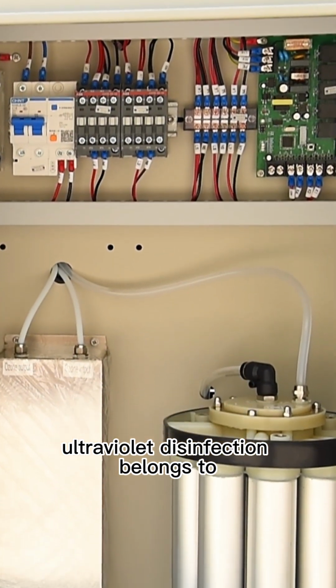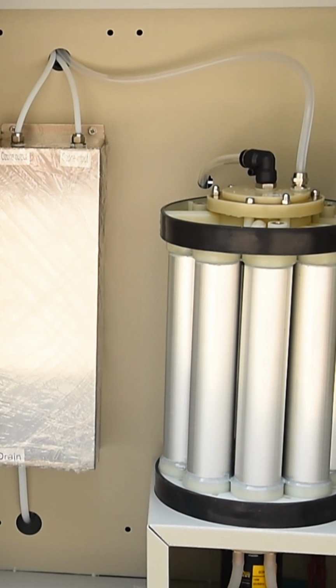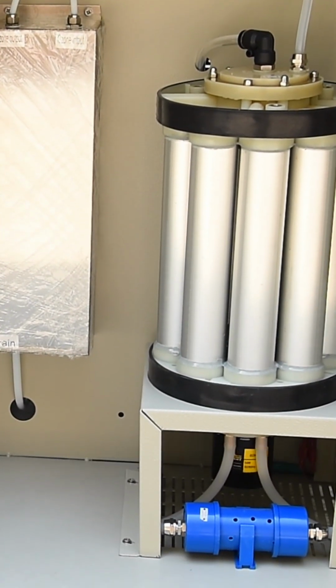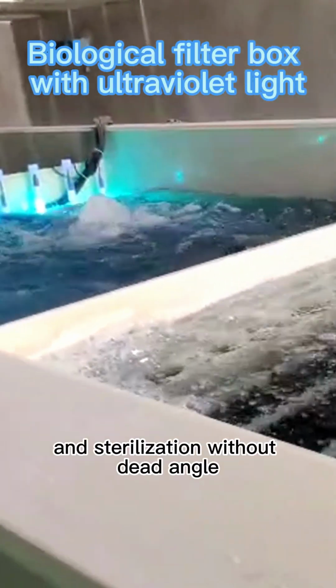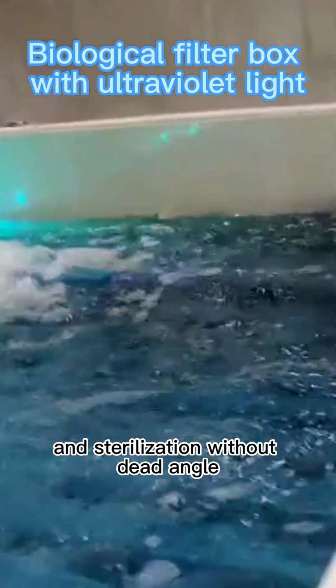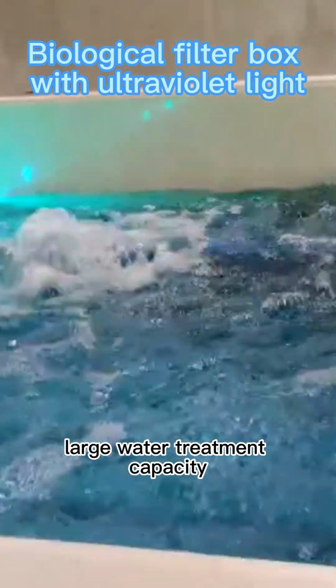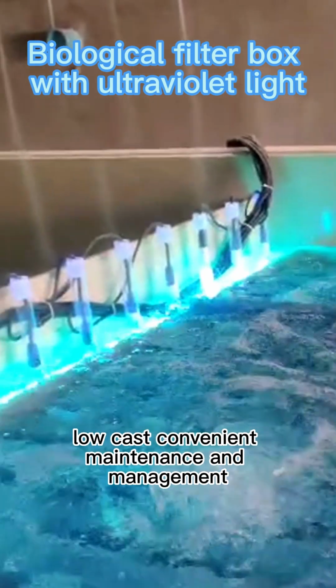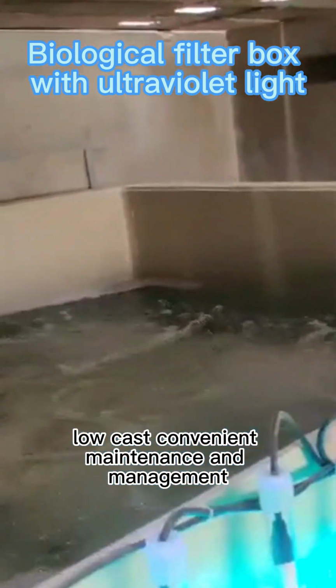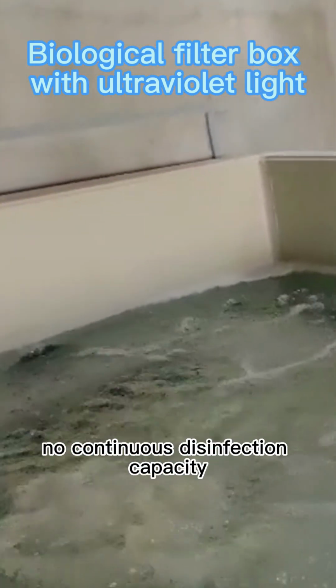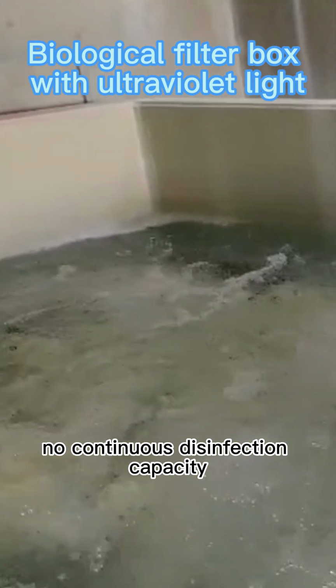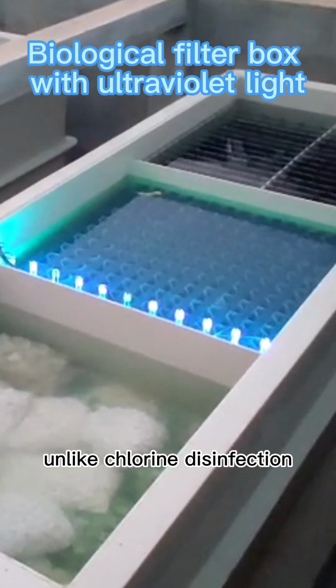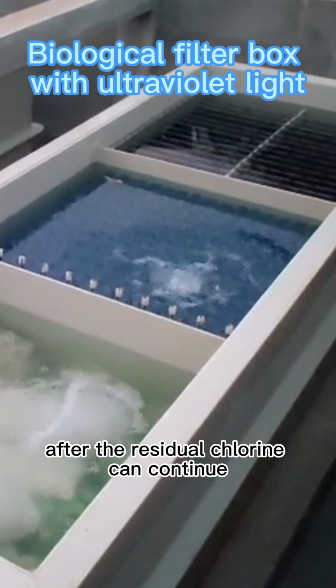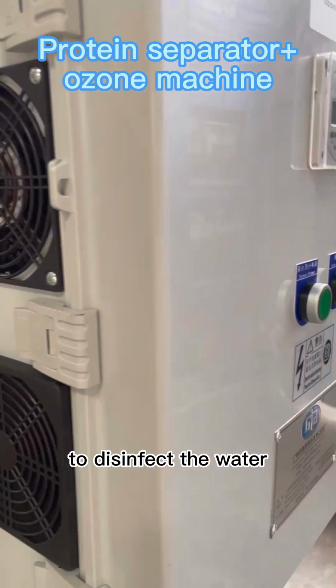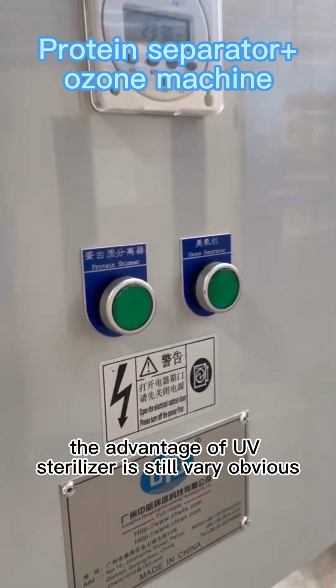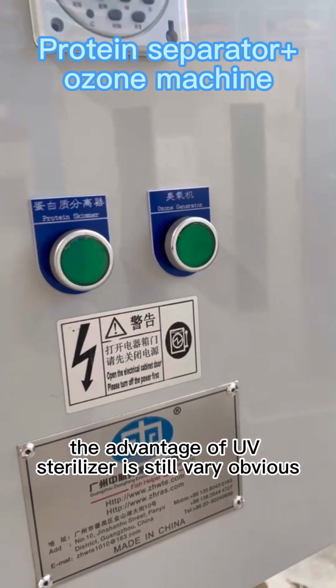Ultraviolet disinfection belongs to physical disinfection. It has high sterilization efficiency, a high sterilization rate, and sterilization without dead angles, a large water treatment capacity, low cost, and convenient maintenance and management. The disadvantage is that there is no continuous disinfection capacity, unlike chlorine disinfection, where residual chlorine can continue to disinfect the water. But overall, the advantages of the UV sterilizer are still very obvious.